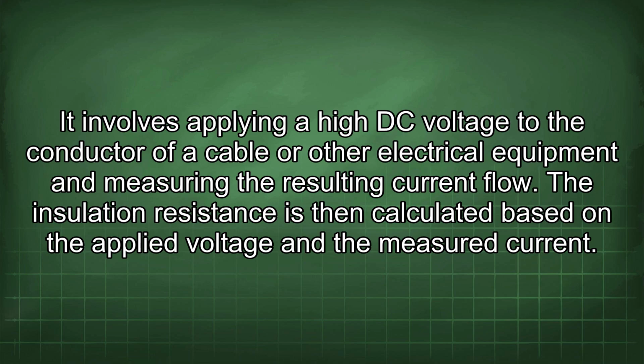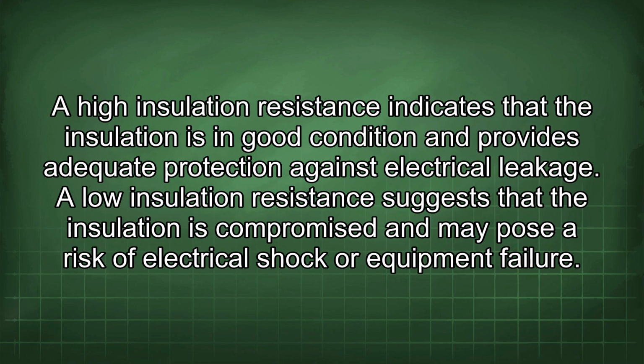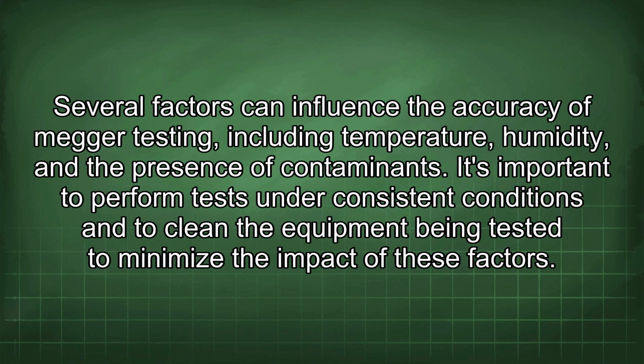The insulation resistance is then calculated based on the applied voltage and the measured current. A high insulation resistance indicates that the insulation is in good condition and provides adequate protection against electrical leakage. A low insulation resistance suggests that the insulation is compromised and may pose a risk of electrical shock or equipment failure. Several factors can influence the accuracy of Megger testing, including temperature, humidity, and the presence of contaminants.